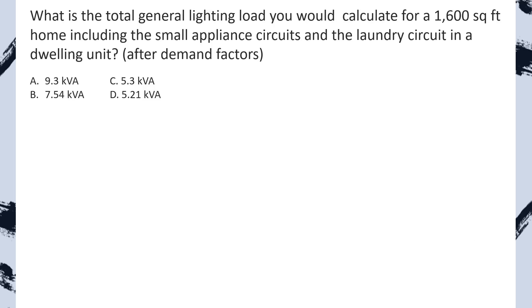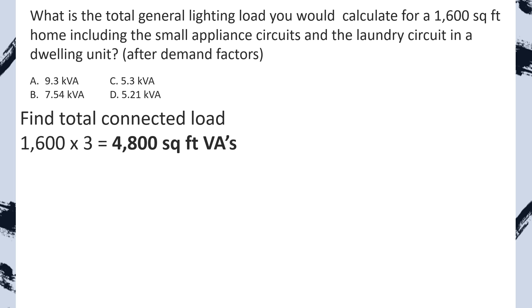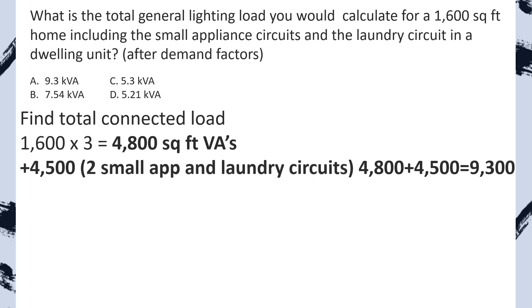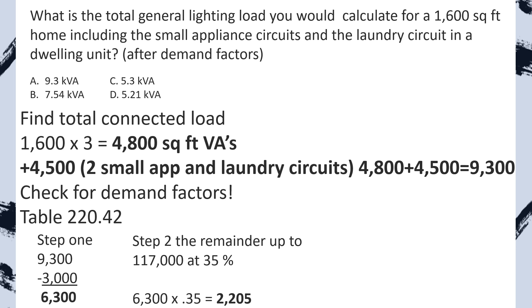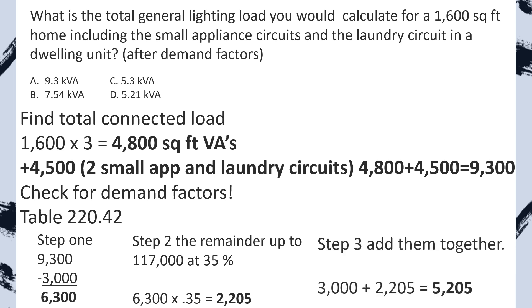What is the total general lighting load you would calculate for a 1,600 square foot home, including the small appliance circuits and the laundry circuit in a dwelling unit after demand factors? Note that on your examination, they will not mention the small appliance and laundry circuits — you just have to know that anytime you're doing the total general load or a whole house load calc, you have to tack on that 4,500 VAs. Step one: find our total connected load. We take 1,600 square feet multiplied by three VAs per square foot, which equals 4,800 VAs. Now we tack on our 4,500 for our two small appliance and one laundry circuits. Then we check for demand factors and head to table 220.42. We take our first 3,000 at 100%, then we take that remainder at 35%, total the two back together, and we select D. Great job.